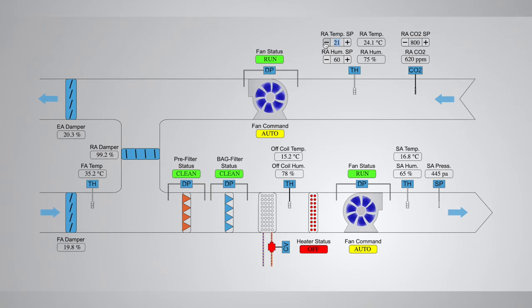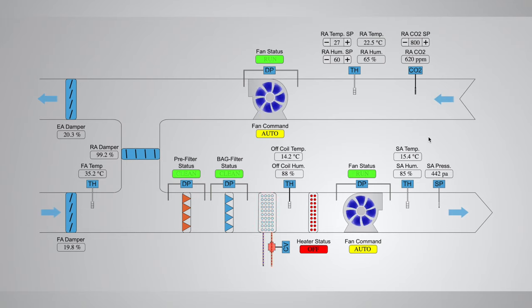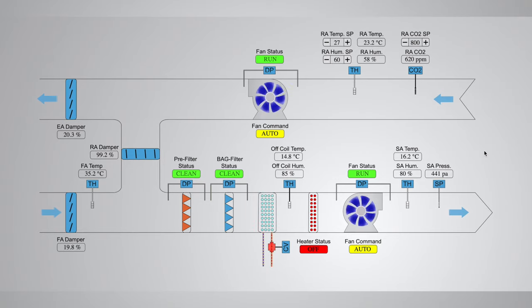If the set point is lowered again, the PID controller will open the control valve actuator again to match the set point. If the set point is increased above the return air temperature, the control valve will be closed as determined by the PID controller. This return air temperature control is only applicable for 100% return air type AHUs where it is 100% return air from the space. If the AHU is supplying to multiple areas and rooms with multiple VAVs and not 100% return, then the supply air temperature will be used to maintain the space temperature, which will be covered in a separate video. If you want to understand more about the AHU cooling principle, I recommend you watch my AHU cooling principle video.